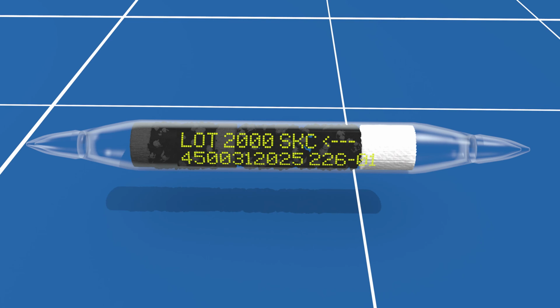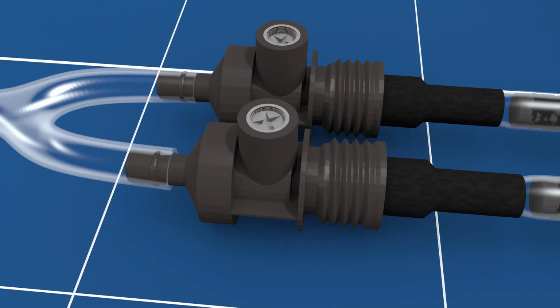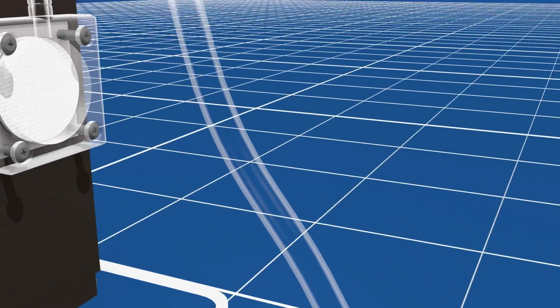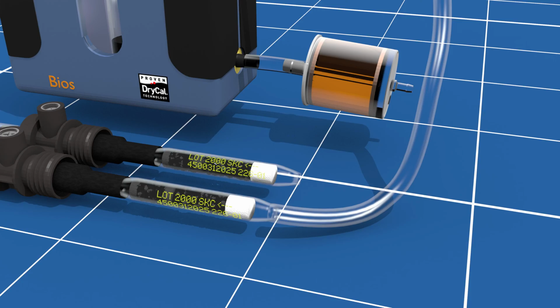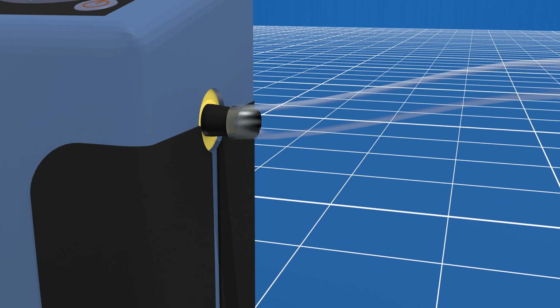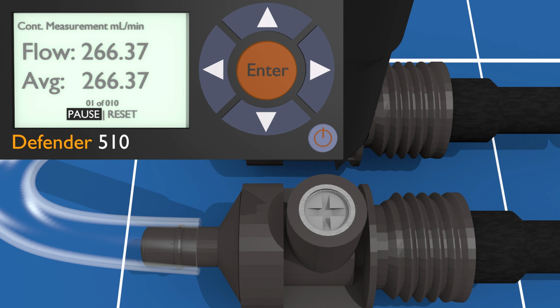Use appropriate sample tubes for your sampling and cut off the ends with the arrow pointing to the holder. Insert your sample tubes into adjustable flow tube holders. Connect the sampling train to the pump. Using flexible tubing, connect one of the 2 sampling tubes to the flow meter. Adjust to the specified flow using the flow adjust screw on the tube holder.